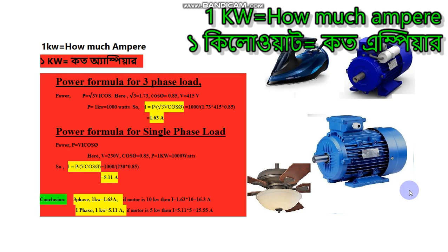This gives us an ampere rating of 5.1 amperes — that is the current consumption of a single-phase motor or load. So in conclusion: for a three-phase load, 1 kilowatt equals 1.63 amperes, and for a single-phase load, 1 kilowatt equals 5.1 amperes.